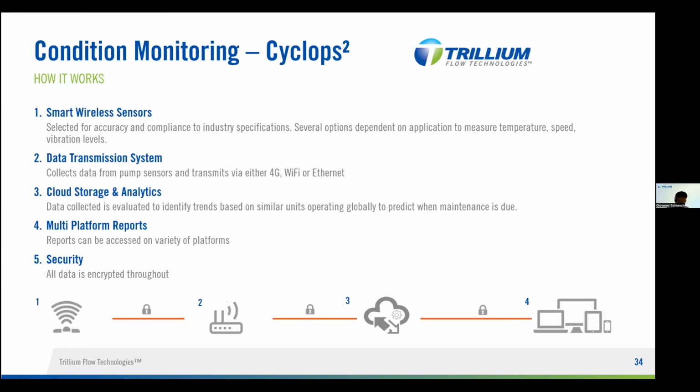We have also a further option in case the customer does not allow installation of dedicated wireless instrumentation, proposing as a further solution collecting data through a data recorder directly connecting to the plant PLC, that is using signals coming from available project or customer instrumentation. In this way, providing direct transmission of all available data to headquarters.